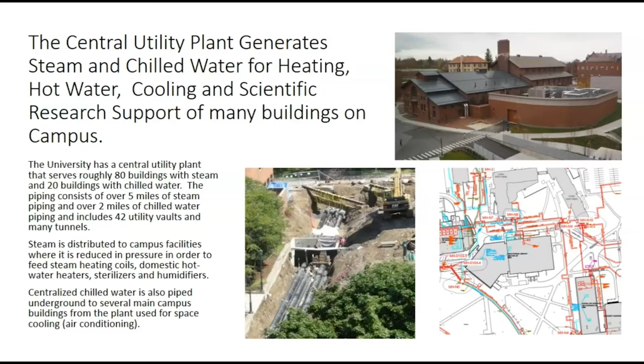For a little background, we have a central utility plant that serves over 80 buildings with steam and 20 buildings with chilled water for heating and air conditioning systems. We have over 5 miles of underground steam piping and over 2 miles of chilled water piping throughout campus, and 42 utility vaults which house valve work, trap assemblies, and other equipment that maintain that distribution.